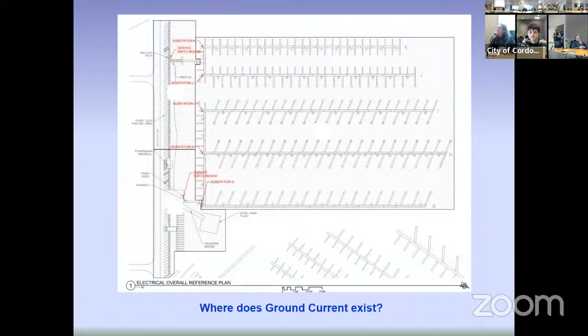This is our harbor here, and it's kind of hard to see, but what I wanted to illustrate here is where we have our circuit protection. So of course, each pedestal will have its own circuit breakers and with ground fault relays. They're all set for 30 milliamps. But at the head of each of the main floats is a substation. And the substation is there with a transformer and a large distribution panel. The distribution panel provides the feeders going out to the pedestals.